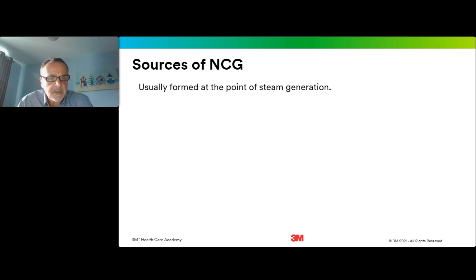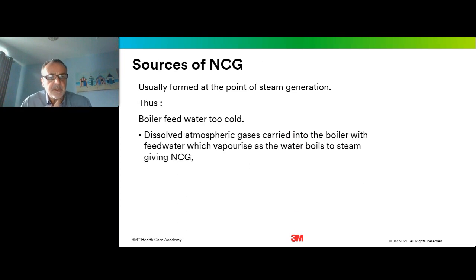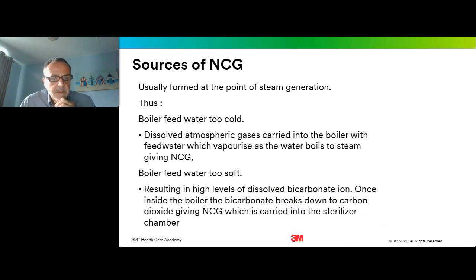So if we consider the sources of non-condensable gases, they're usually created during the steam generation process. So first of all, the boiler water, the boiler feed water could be too cold. Cold water dissolves an awful lot of atmospheric gases. I'll show you that in a second. And when this cold water boils in the boiler, those gases will be released and be carried forward with the steam into the chamber of the steriliser.